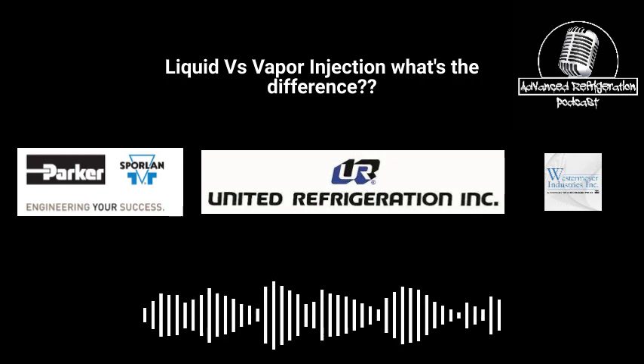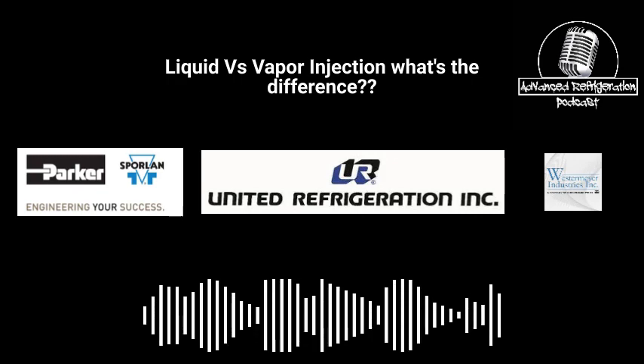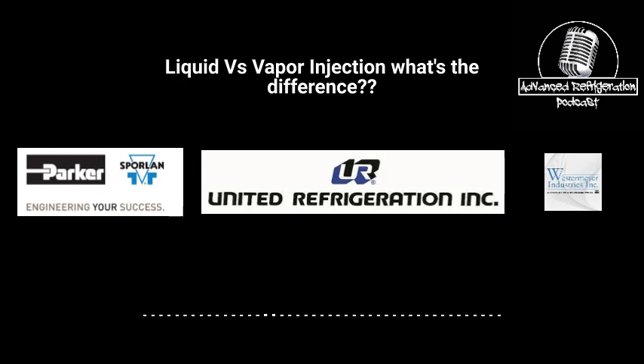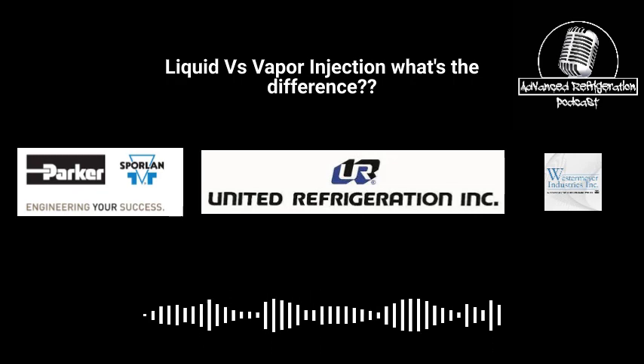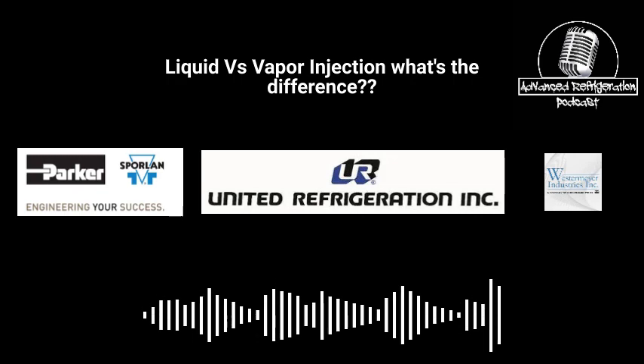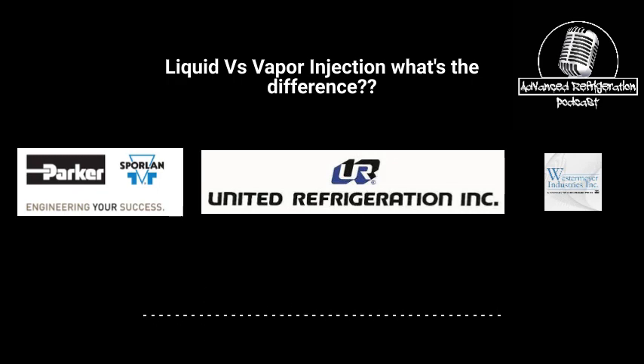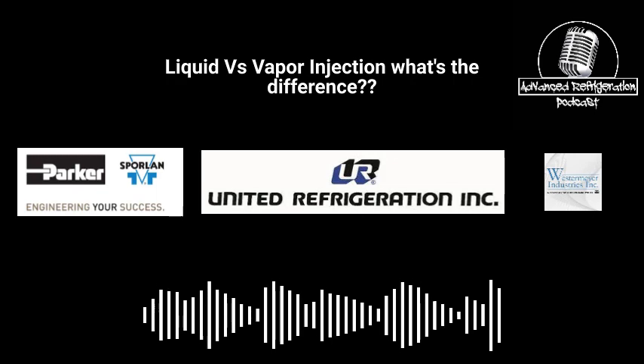So that's where you get the random oil failures. You'll get there and there's nothing locked out, and you'll see that the OMB resets 5 times on its own before it hard locks out. That's where you get these random oil failures and proof failures, because you're flooding back so badly that it's not filling up the compressor fast enough for it to lock out. Yeah, 100%. So that's why that happens.